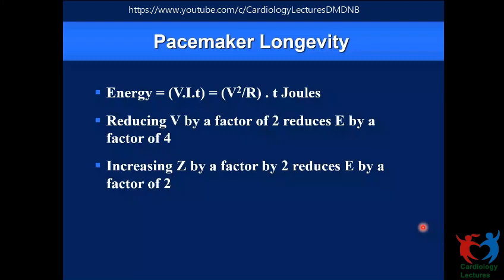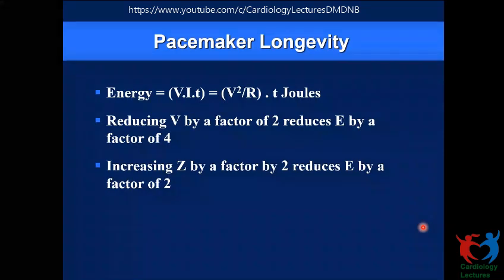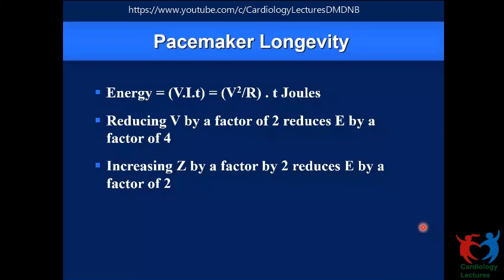Okay, sir. So what we are talking about is a combination of both. When we actually do the practical measurements, it's a combination of both. So that means the conductor impedance is lower. The impedance that is relatively higher is the interface, the polarization impedance. That's what we are getting. So when that is higher, it becomes more efficient, so you get a lower threshold and it allows you to program a lower output. So polarization impedance is the one at the tip. Is it the same or different, sir? Yeah, so it happens at the tip.